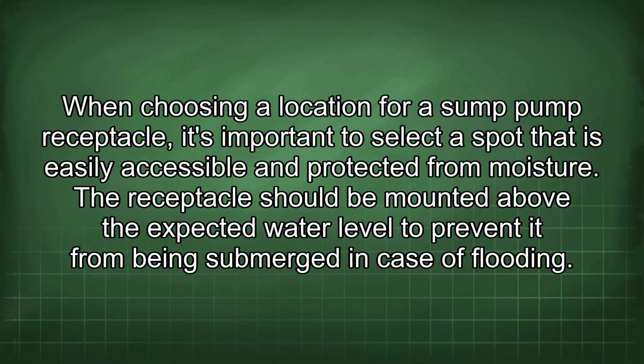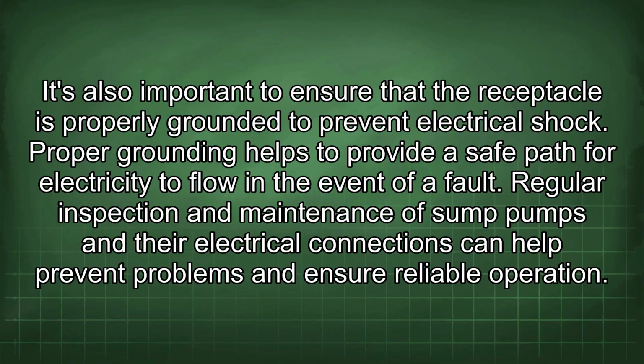When choosing a location for a sump pump receptacle, it's important to select a spot that is easily accessible and protected from moisture. The receptacle should be mounted above the expected water level to prevent it from being submerged in case of flooding. It's also important to ensure that the receptacle is properly grounded to prevent electrical shock. Proper grounding helps to provide a safe path for electricity to flow in the event of a fault.